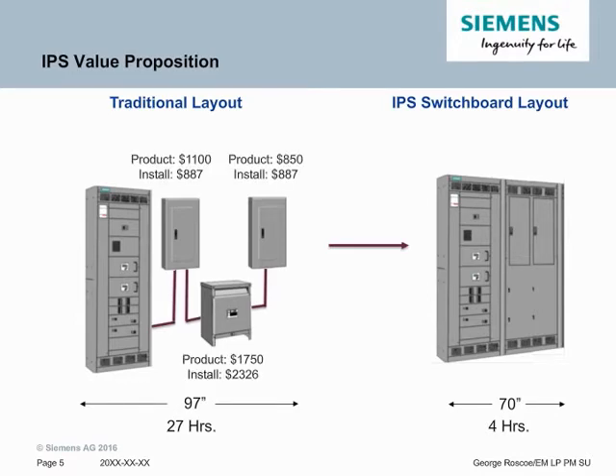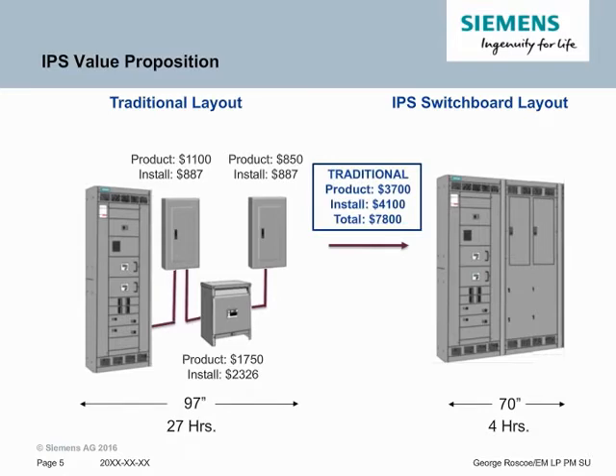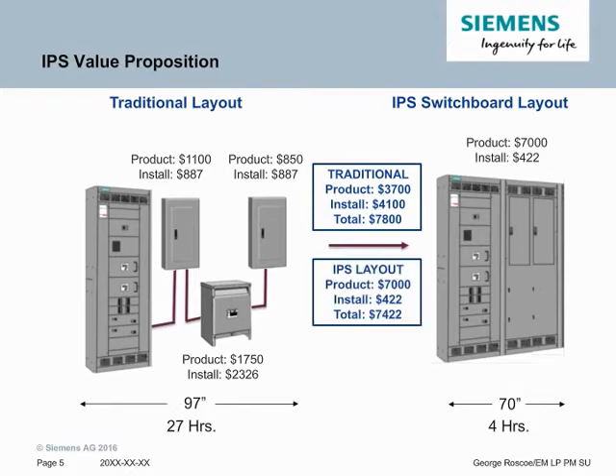When looking at the value proposition, it's important to compare a traditional layout installed versus the IPS switchboard layout. When you look at installation and product cost combined, the installation cost is about half of the total cost. For an IPS switchboard, the product cost is much higher, but the install cost is about 10% of the traditional cost of install. This gives a savings of about 5% versus traditional layouts. This needs to be considered as a wall-to-wall savings, and the IPS switchboard will come out ahead.